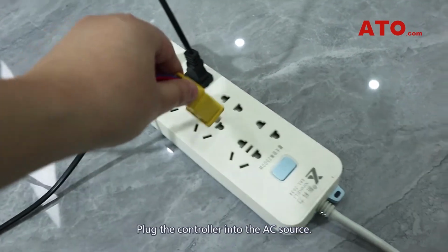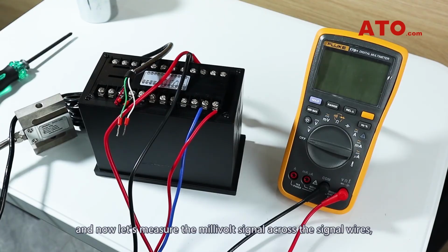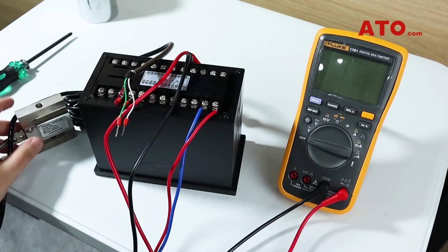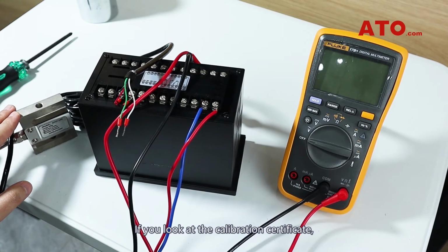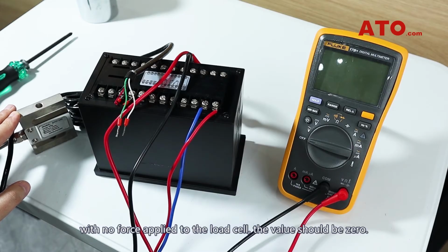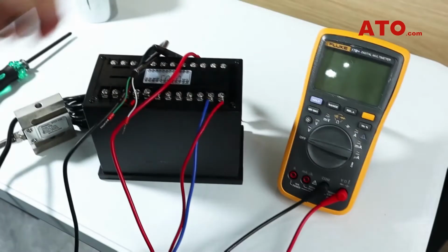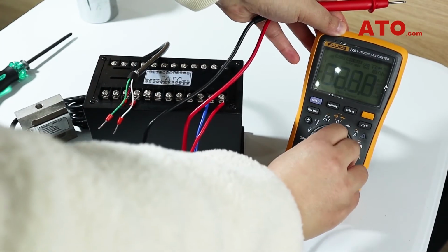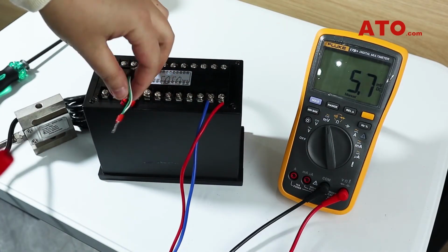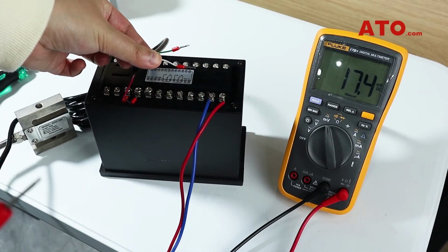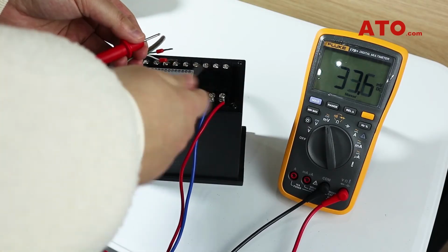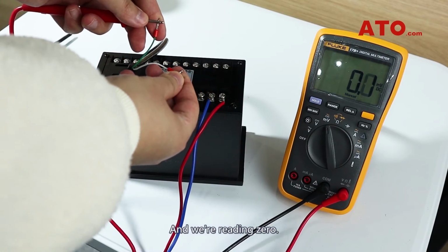Plug the controller into the AC source. And now let's measure the millivolt signal across the signal wires, namely the green and white wires, and we've got the millivolt reading. If you look at the calibration certificate, with no force applied to the load cell, the value should be 0. And we're reading 0.